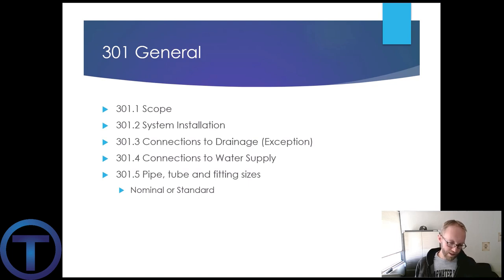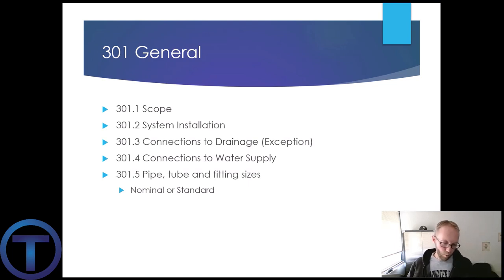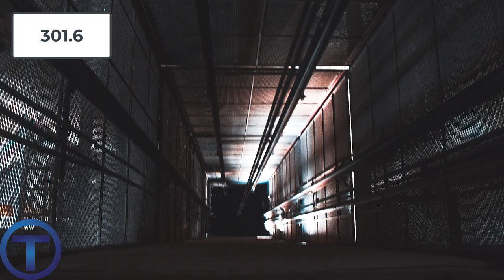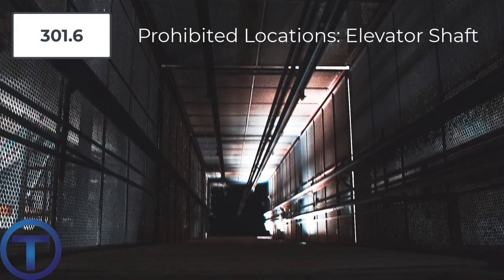301.6 Prohibited locations — there are some places that plumbing should not be installed. One of those is in an elevator shaft. One exception is they will allow a sump pit and sump pump so that if the hydraulics in that elevator should fail, there's a way to get rid of all that oil without having to swim in it, and it would have to go through an indirect waste receptor — catching that oil and separating it instead of dumping it down the regular sanitary sewer drain.